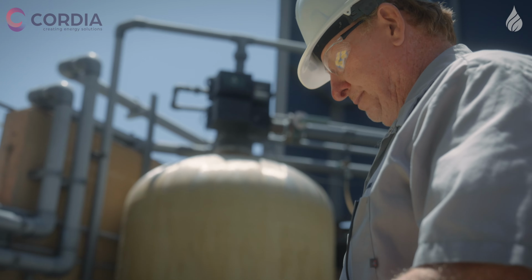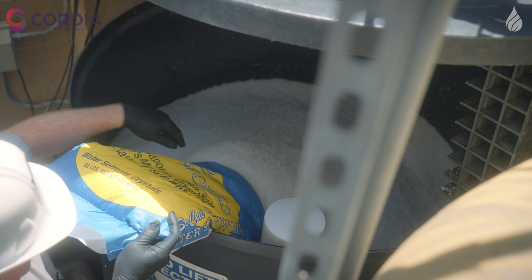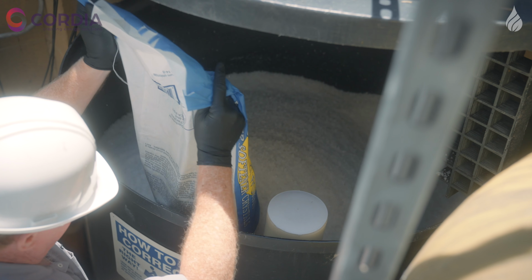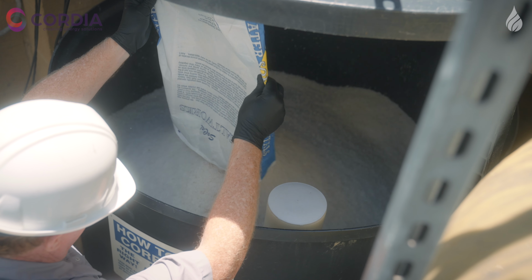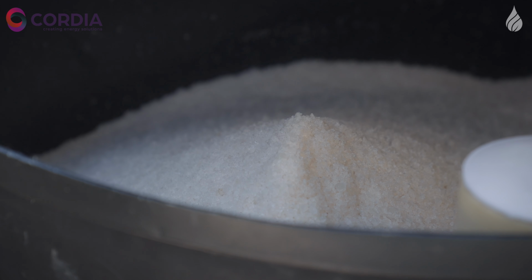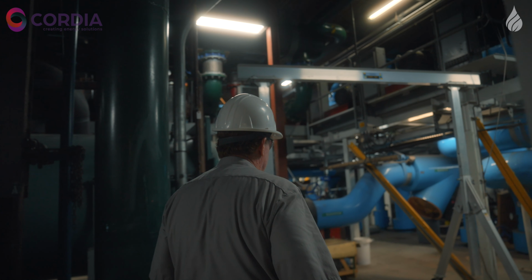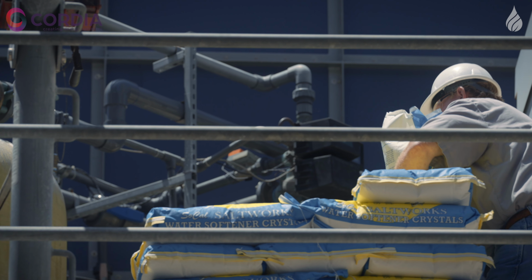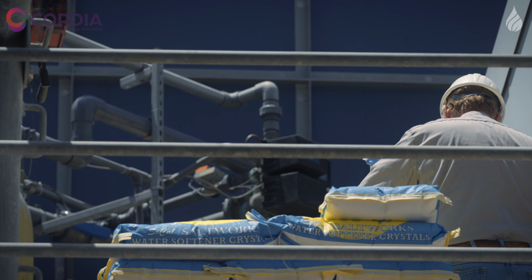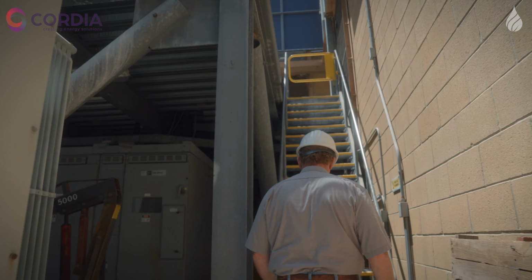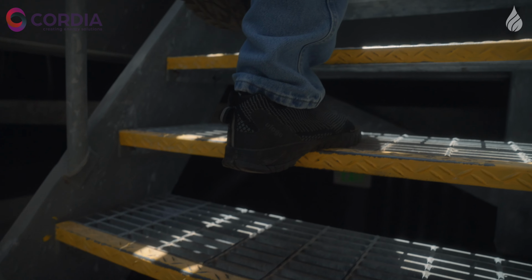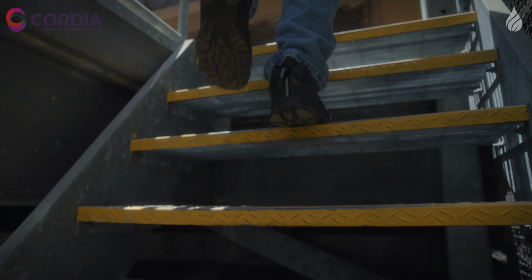The biggest involvement we have with the program is doing daily water tests to make sure everything stays within specs, and then adding salt to the brine tanks during normal daily operations to make sure the salt tanks stay full. And then washing off the inlet louvers during the wintertime. That's basically it. The service from Capture H2O has been nothing but fantastic, I get along with the entire crew. The service tech comes at least once a month, and whenever we have issues, he's always on call, on the spot, quick response, and always good results.